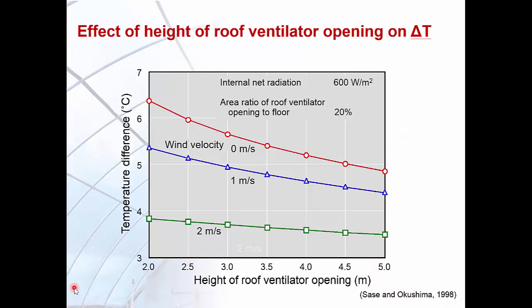Here is an example demonstrating the effect of the height of the roof ventilator opening from the floor on the temperature difference between the greenhouse interior and exterior. This example is from a naturally vented greenhouse without side vents, using a heat balance equation under steady-state conditions, assuming an internal net radiation of 600 watts per meter square and a roof ventilator to floor opening area ratio of about 20%. The data shows that temperature rise decreased as the height of the opening increased for all cases of external wind speed.